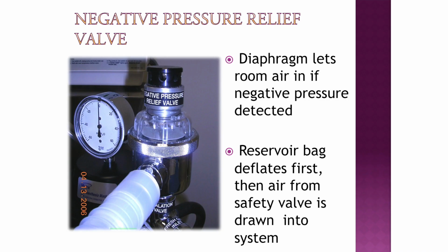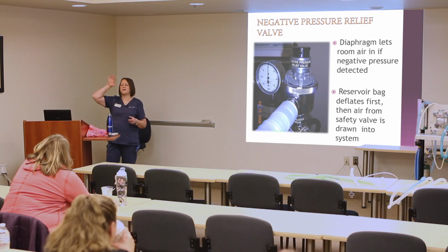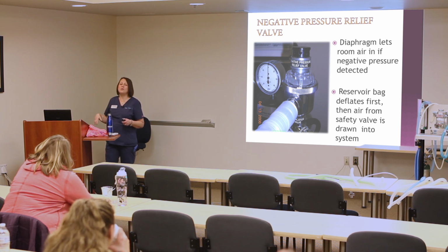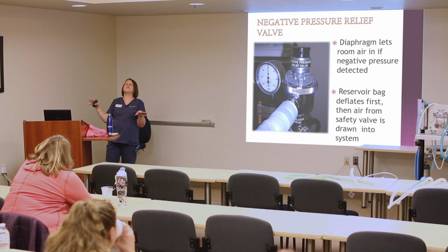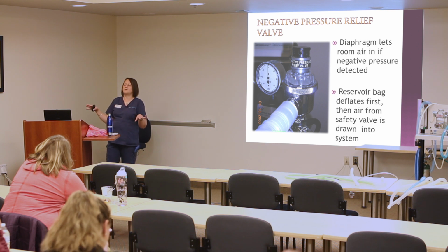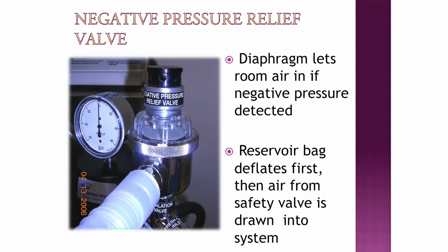Now we do have some of these negative pressure relief valves, and where these came from, does anybody go to the dentist and get the gas, the nitrous oxide? So in case the dentist ever forgot about you while you're all sailing in your chair and they ran out of oxygen and they ran out of gas, this negative pressure relief valve would let you not die in the dentist chair, so that should be very comforting to you. What it does is when it senses negative pressure in the circuit, so sucking rubber and the animal's trying to breathe, it actually lets room air into the circuit. So that's the only thing these do.